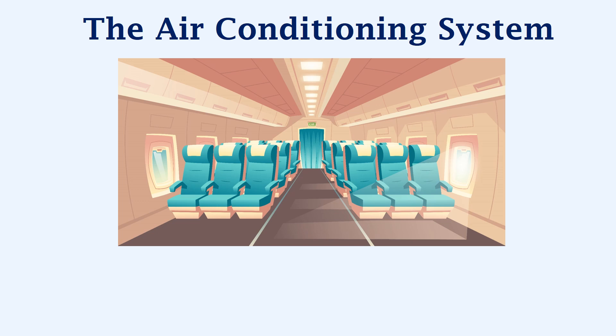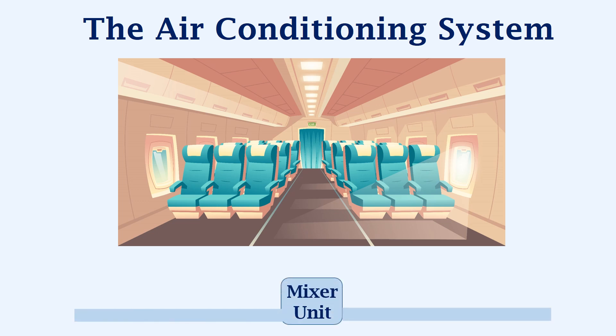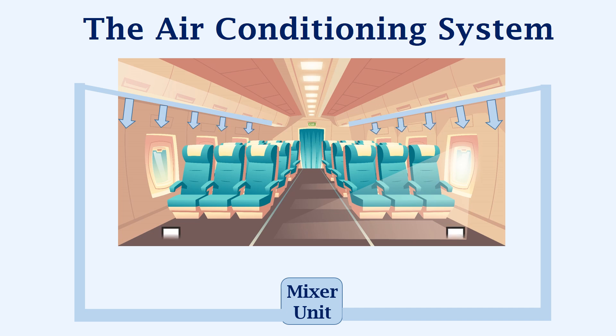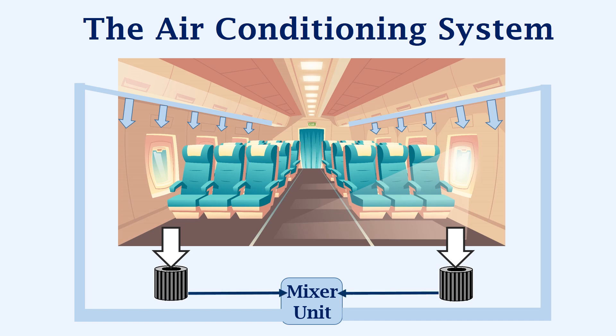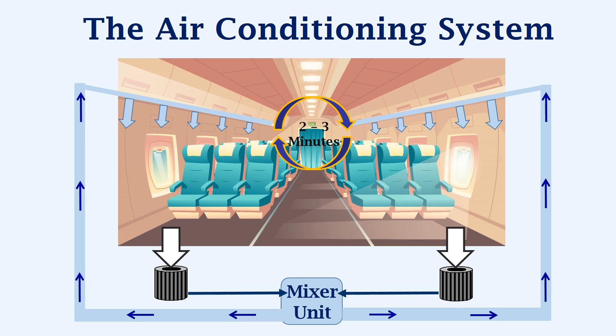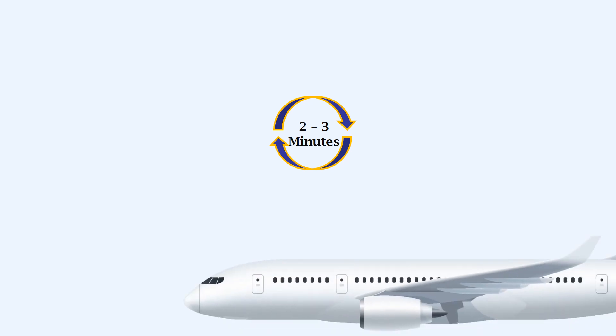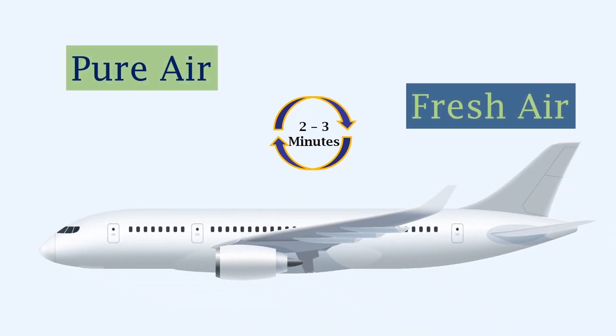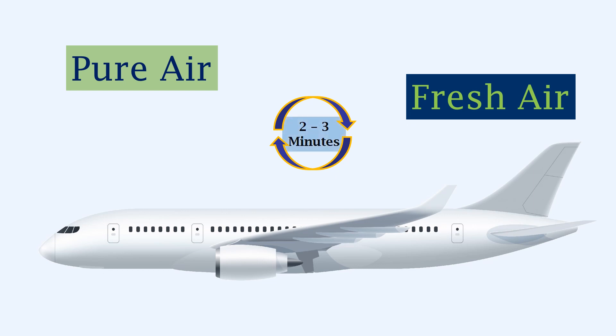To get a better understanding of the air distribution and purification process, let's take a different look inside the cabin. The cold air from the mixer unit is distributed via vents, as shown here. The impure air is taken through vents in the cabin floor, and this impure air gets purified as it passes through the HEPA filter. From the HEPA filter, the pure air is sent to the mixer unit, which mixes it with fresh air, and this mixed air is sent back to the aircraft. This continuous process ensures that the air inside the aircraft gets renewed every two to three minutes, thus ensuring that the air inside the aircraft is safe.